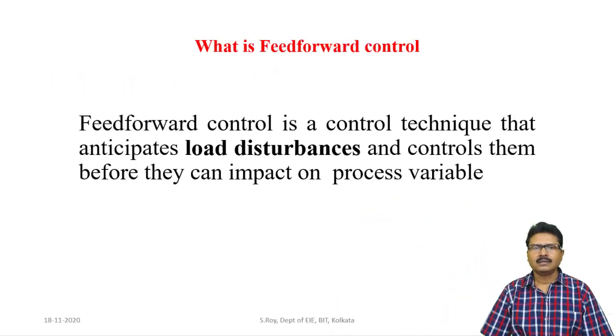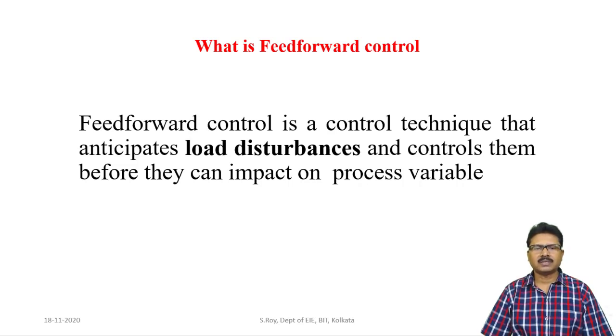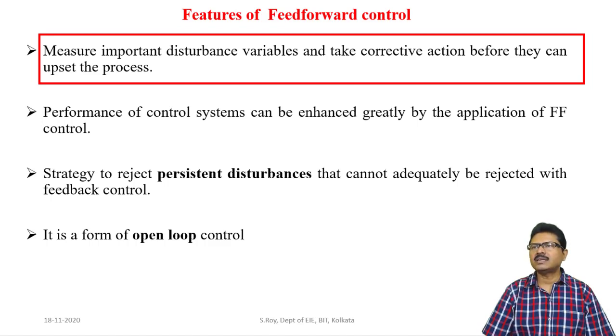Feedforward control is a control technique that anticipates load disturbances and controls them before they can impact the process variable. The main parameter considered is load disturbances — it measures those disturbances and uses a mathematical model to calculate what the output of the process should be, producing a signal that controls the manipulated variable to maintain the controlled variable at the set point. Corrective action is taken before disturbing the process variable.